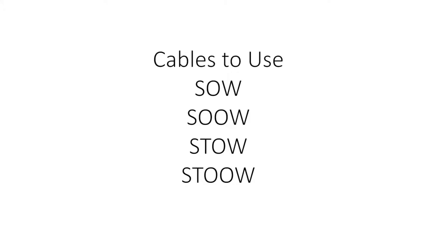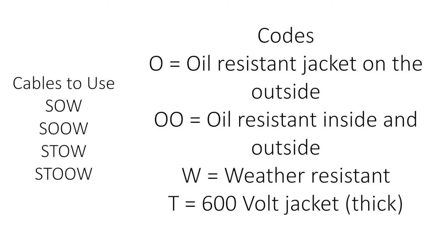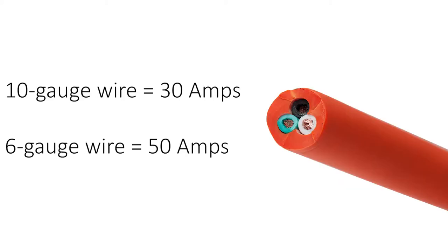When it comes to cables, they should have a rating of SOW, SOOW, STOW, or STOOW. What do these codes mean? O stands for oil resistant jacket on the outside of the cable. OO stands for oil resistance on the inside and outside of the cable. W represents weather resistant. T means it'll be a thick 600 volt jacket. You should also make sure to have a 10 gauge wire for 30 amps and 6 gauge wire for 50 amps.